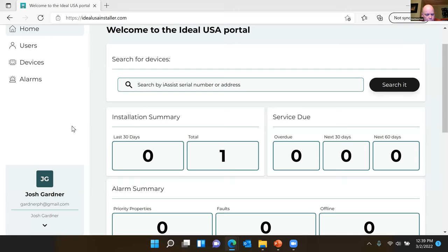Perfect. Josh, quick question. The onboard controller, does the Triangle Tube onboard control board have a 24-volt common output on it? Currently, no. Okay. It does not. We have a 120 output for an outlet or lights in the boiler, whatever you want. And you could run a transformer in that. But right, we do not have a 24-volt dedicated output, which 100% we know we need. And on the next version of boilers, 100% we'll have it. We got confirmation on that. Thank you, Josh.